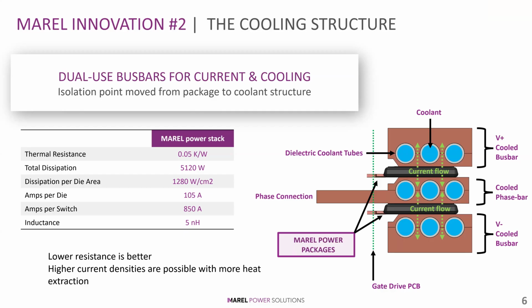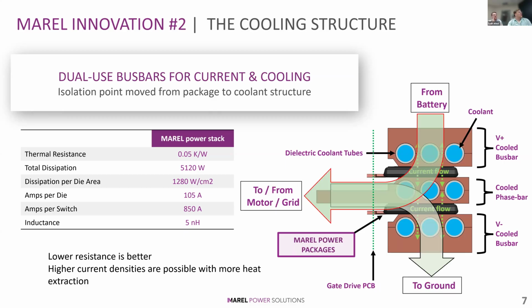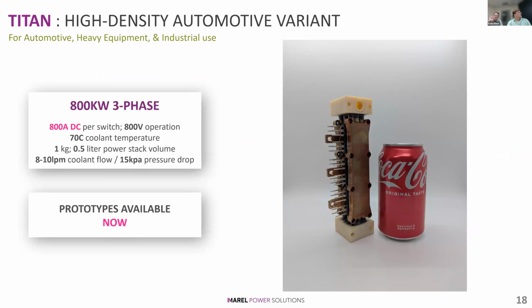Next question: does placing the modules on the bus bar eliminate the separate heatsink? The bus bars are copper or aluminum, and the power modules are soldered directly to those bus bars, so yes, there are no auxiliary heat sinks attached to the power modules themselves. It is a coolant loop, so somewhere in the system you'll need a radiator. Using water glycol instead of a dielectric fluid lets us drop into a lot more existing applications with minor changes to the coolant loop system. For an automotive application, for example, this is just integrated into the vehicle cooling system, using the same coolant the rest of the vehicle would use.